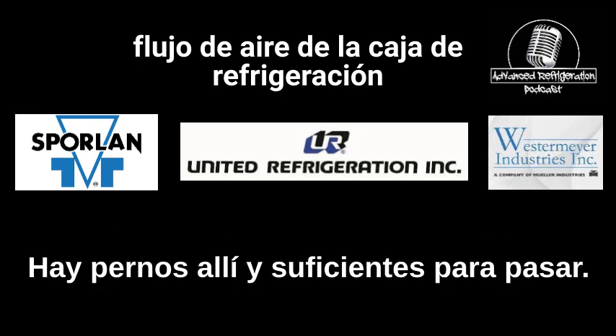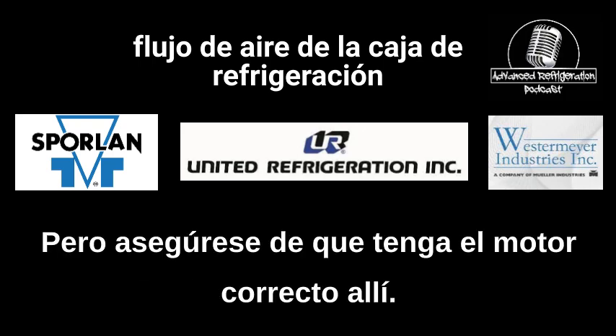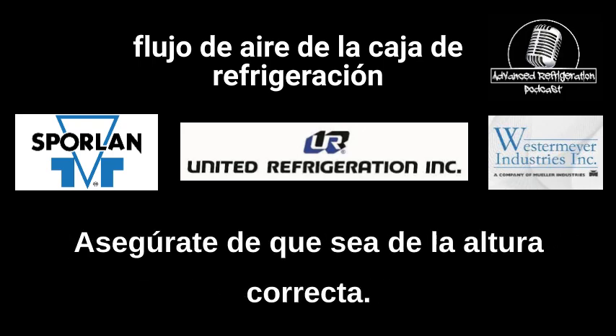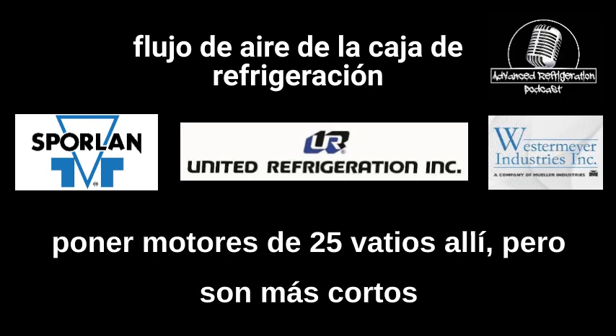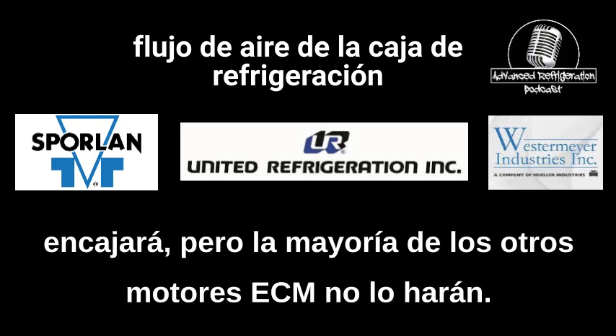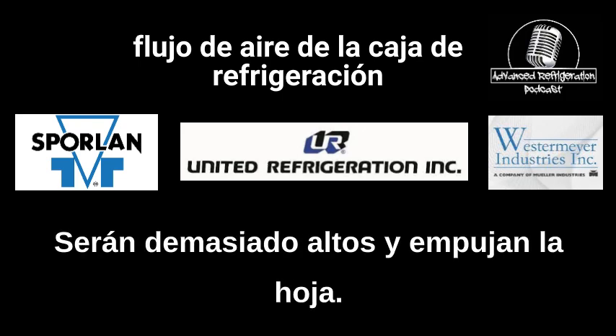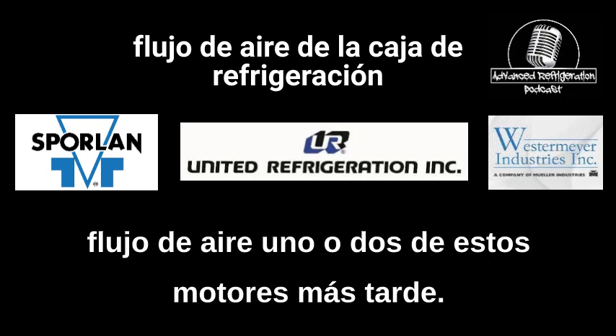There's bolts in there, and enough to get you by. So that's one thing, but make sure it's got the right motor in there. Make sure it's the right height. Like Hussmann puts in their frozen food doors, they put 25-watt motors in there, but they're shorter than most motors. So that ECM 5411E will fit, but most other ECM motors will not. They'll be too tall, and it pushes the blade farther out of the plenum, and it reduces your airflow.